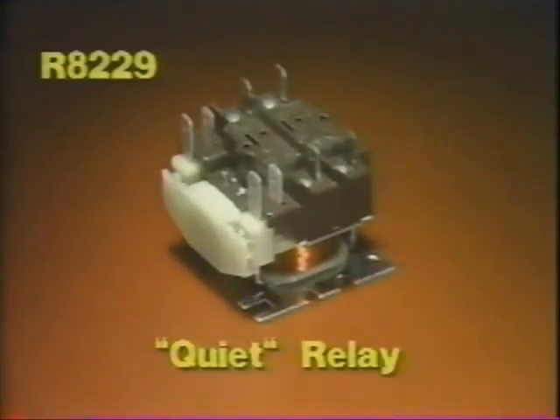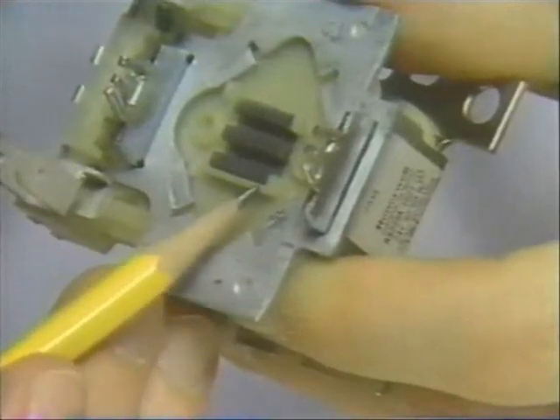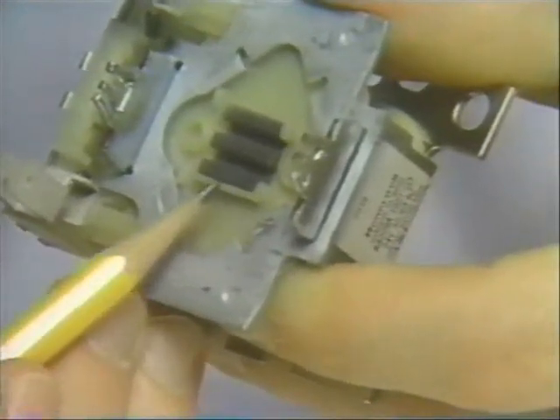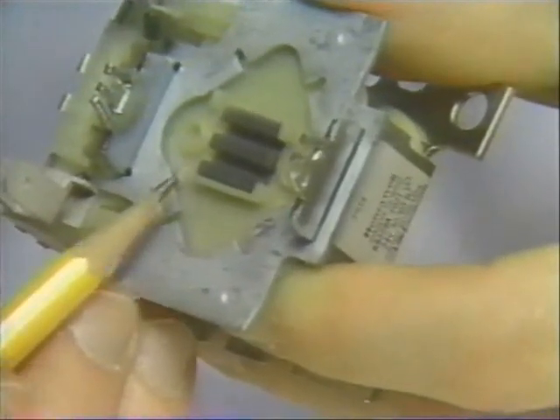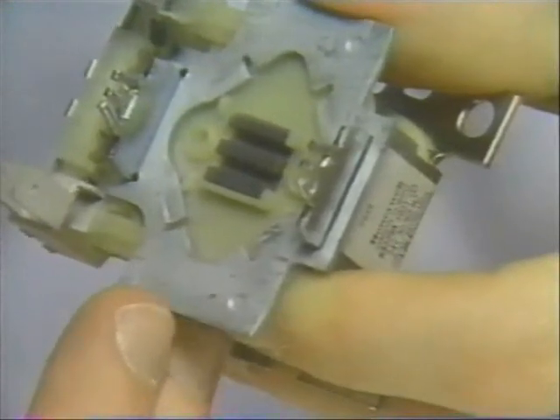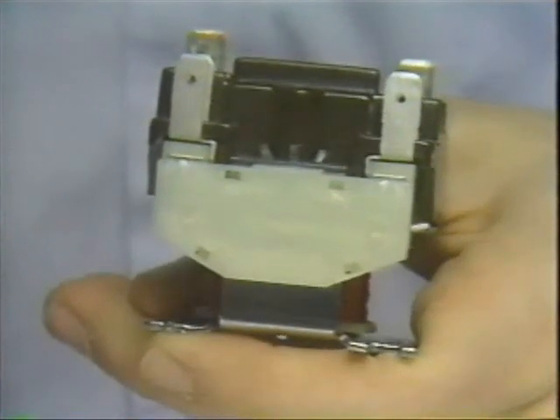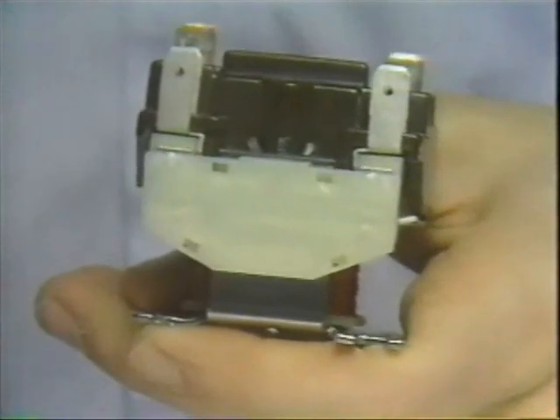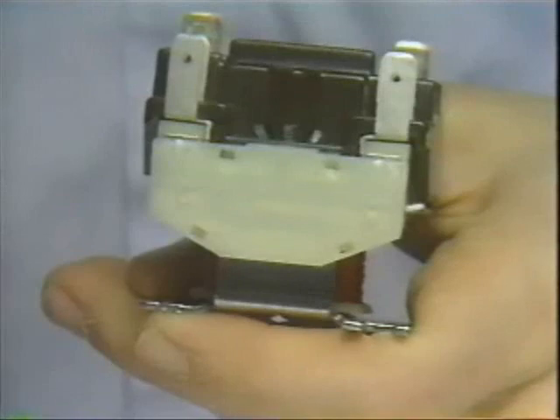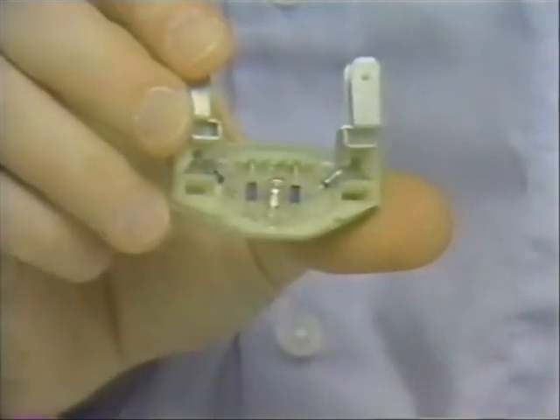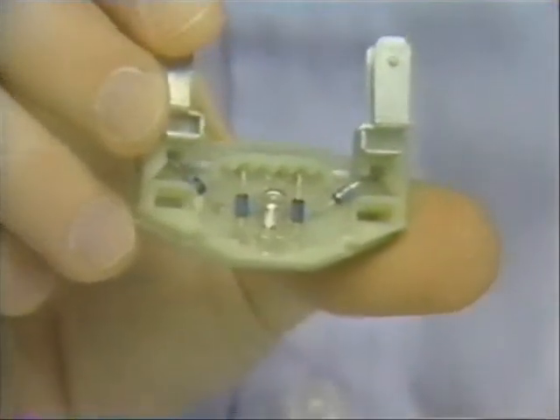Honeywell has developed a special quiet operating relay, the R8229, for electric heating systems. The quiet secret is a nylon bumper that fits over the coil's magnetic core. The bumper cushions the blow of the armature when it pulls in, deadening the sound. For technical reasons, the coil of the 8229 is designed for direct instead of alternating current. A small diode rectifier on the side of the relay converts AC current to DC for the coil.